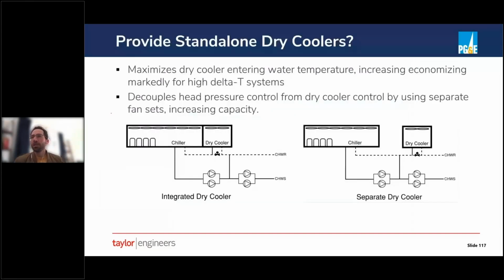All right. One thing to consider is whether you even should be providing standalone dry coolers or taking advantage of the fact that manufacturers do offer this product, whether you have a dry cooler integrated to your air-cooled chiller. From an efficiency perspective, there can be major benefits to actually providing separate dry coolers. So on the left is an example of an integrated dry cooler. On the right is a standalone dry cooler. And I think the critical consideration here, and these are examples of primary secondary system, is where the dry cooler is connected relative to the decoupler.